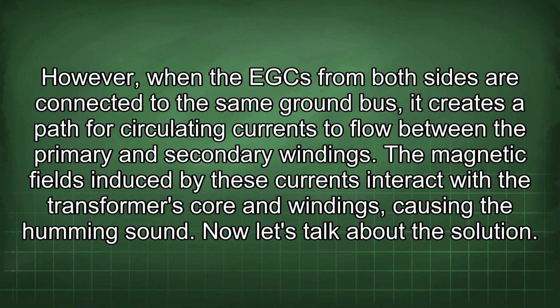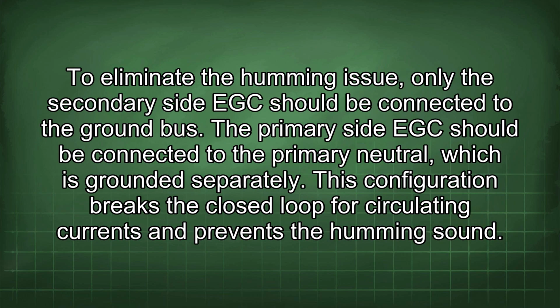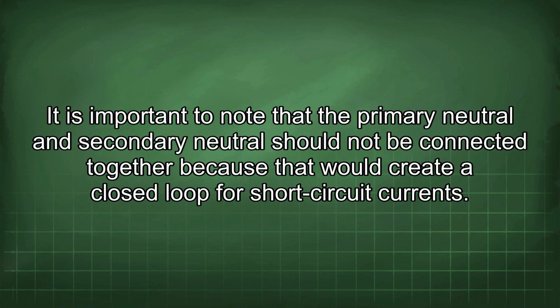Now let's talk about the solution. To eliminate the humming issue, only the secondary side EGC should be connected to the ground bus. The primary side EGC should be connected to the primary neutral, which is grounded separately. This configuration breaks the closed loop for circulating currents and prevents the humming sound. It is important to note that the primary neutral and secondary neutral should not be connected together because that would create a closed loop for short-circuit currents.